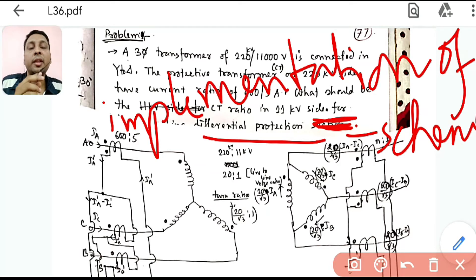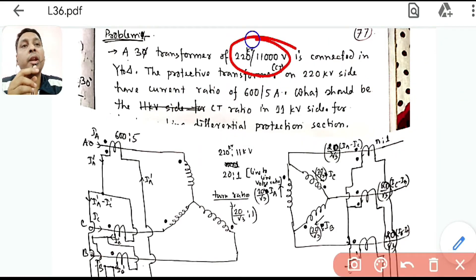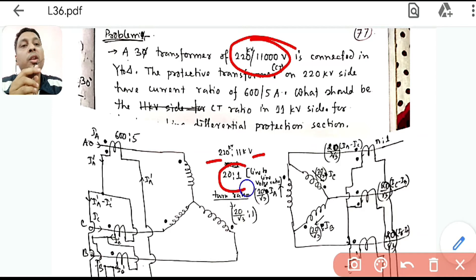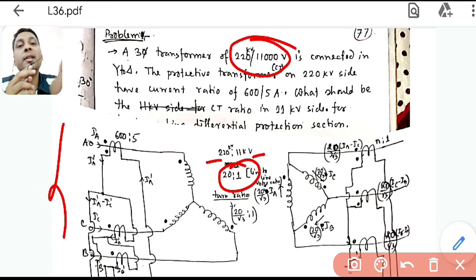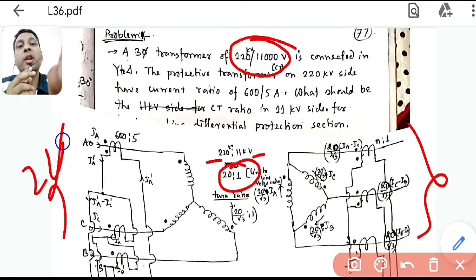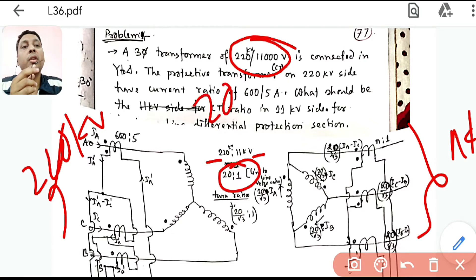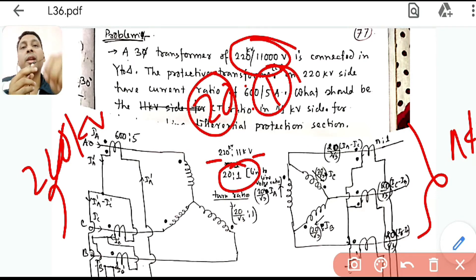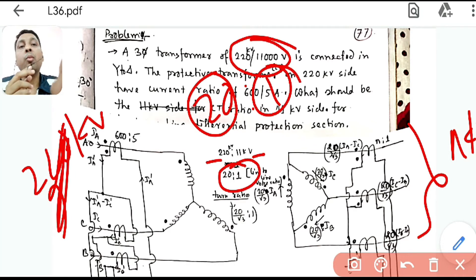Before proceeding, let us draw the connections — once you know the connections the numerical becomes easy. One important point: the ratio 220/11 = 20:1 is the ratio between line voltages, not the turns ratio. It does not mean 20 turns on one side and 1 turn on the other.